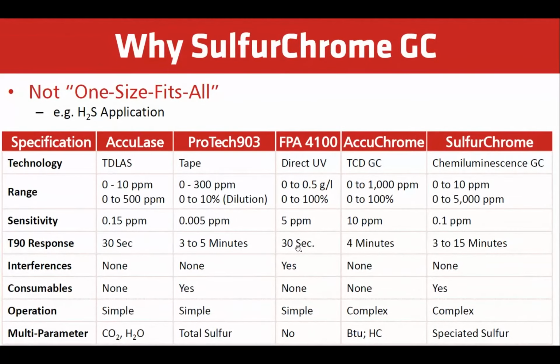Why Sulfur Chrome GC again? Not one size fits all. Some of the technology that we use to measure H2S is the Acculase, which is a TDL. The range is 0 to 10 or 0 to 500 ppm. No interference. Sensitivity is 0.15 ppm. T90 response, 30 seconds. Interference, none. Consumable, none. Operation is simple. For multiple parameters, we can also measure CO2 and H2O in the same analyzer.